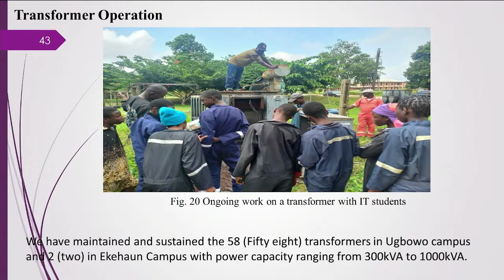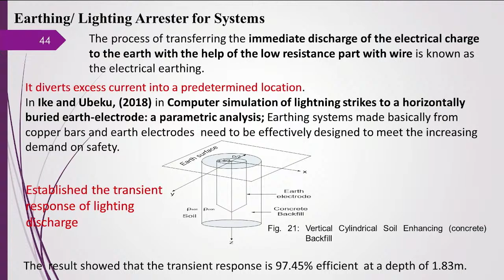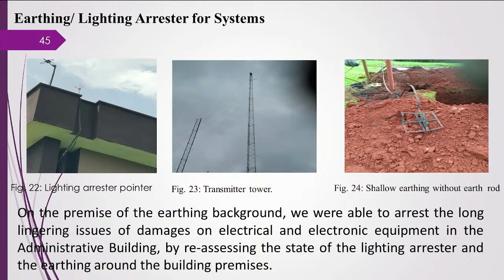In Ike and Ubeku 2018, a computer simulation of lightning strike to a horizontally buried earth electrode, a parametric analysis, we tried to find alternative paths to lightning discharge at the easiest point. This was to establish the transient response of lightning discharge in the installation. The results showed that the transient response is 97.45% efficient at a depth of 1.83 meters. On the premise of the earthing background that we had, we were able to arrest the long lingering issue of damages on electrical and electronic equipment in the administrative building by reassessing the state of the lightning arrestor and the earthing around the building as shown.